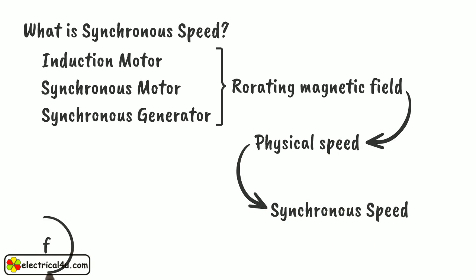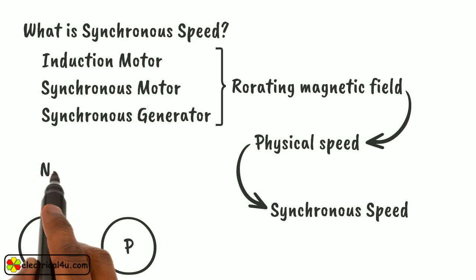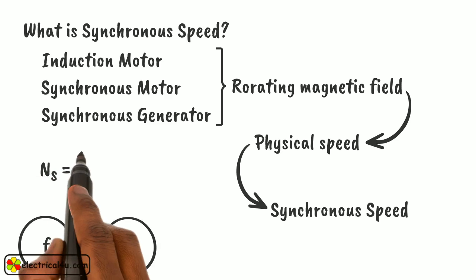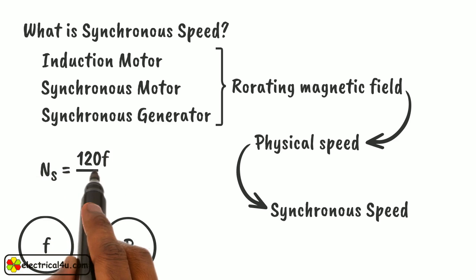It depends upon supply frequency and number of poles in the stator. The equation of the Synchronous Speed is given as Ns equals 120f by p, where f is frequency, p is number of poles, and Ns is Synchronous Speed in RPM.